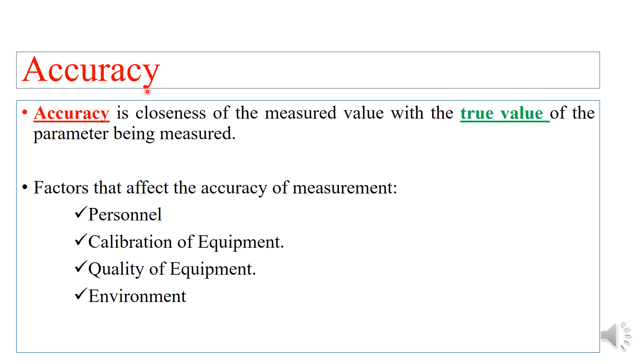Accuracy is the closeness of the obtained result with the true value for any parameter that is being measured or tested. The factors that affect the accuracy of a test procedure are the personnel performing the test, the calibration of the equipment, the quality of the equipment and the reagents, and the environment — room temperature and humidity of the laboratory.